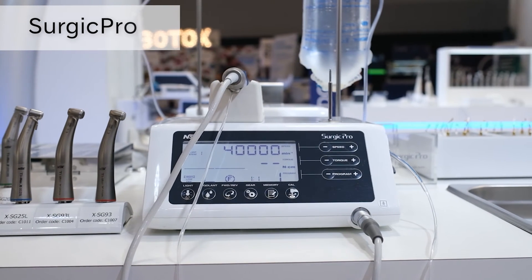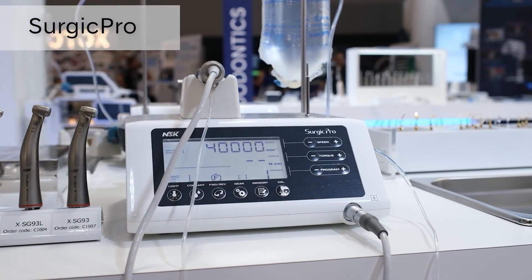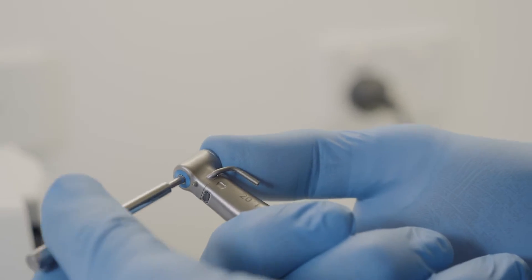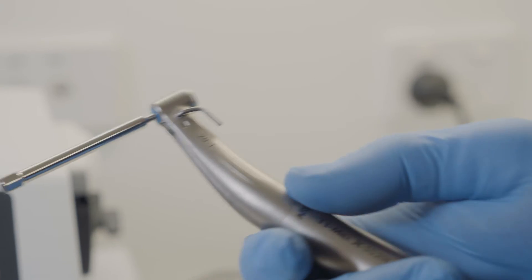SurgicPro incorporates an automatic function to recognise the level of resistance of the attached handpiece and motor. You will require a 20 to 1 handpiece with a calibration burr attached.